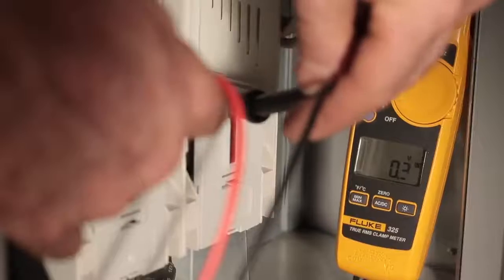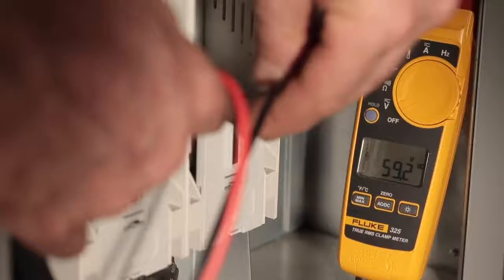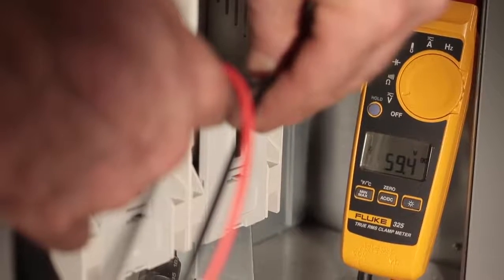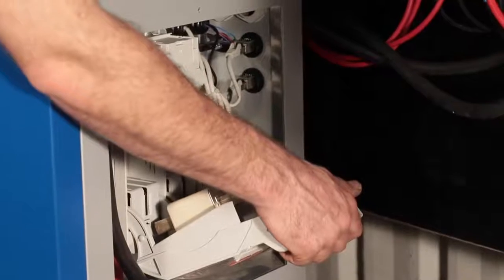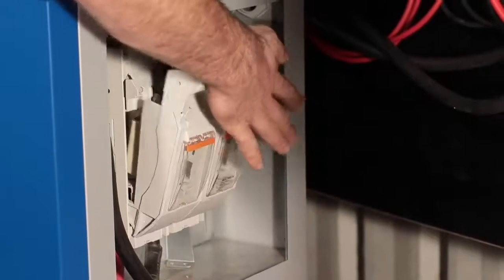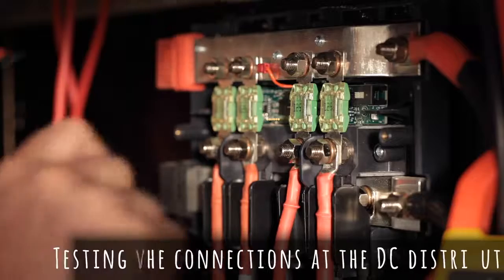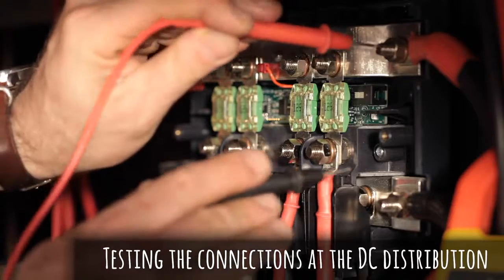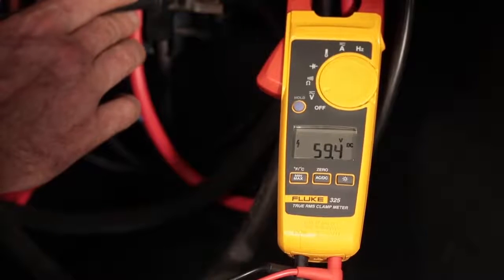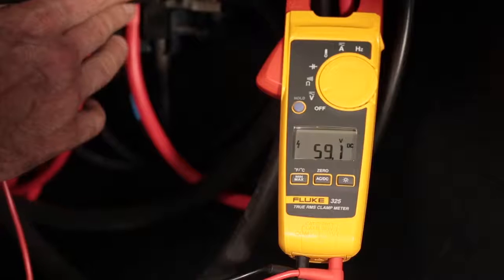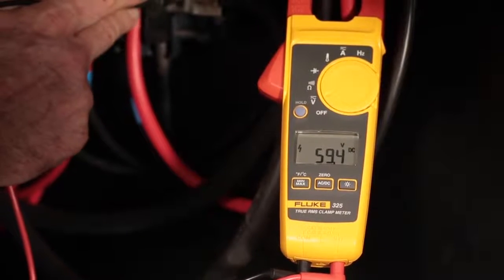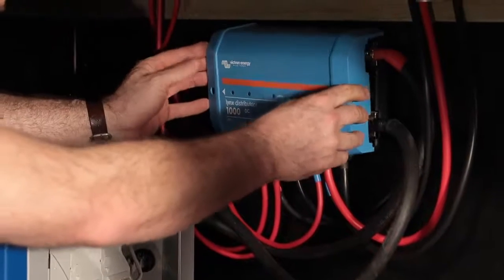Double check to make sure your polarity is correct. Before closing the main fuse to the batteries and switching the battery on, definitely check the polarity. Once you're certain of the polarity, close the main battery fuse. You can now check polarity at the bus bar. Remember, the multis are still isolated at the isolator that's closest to them, so in the event of a reverse polarity situation, they're not going to be damaged. We're going to double check them again.